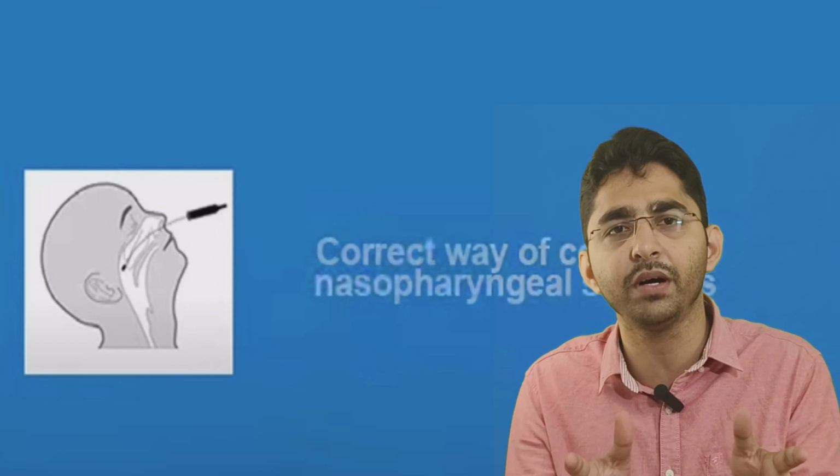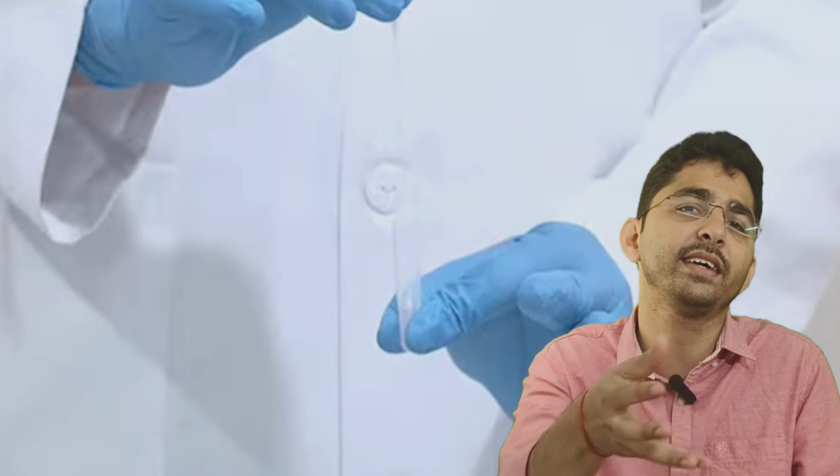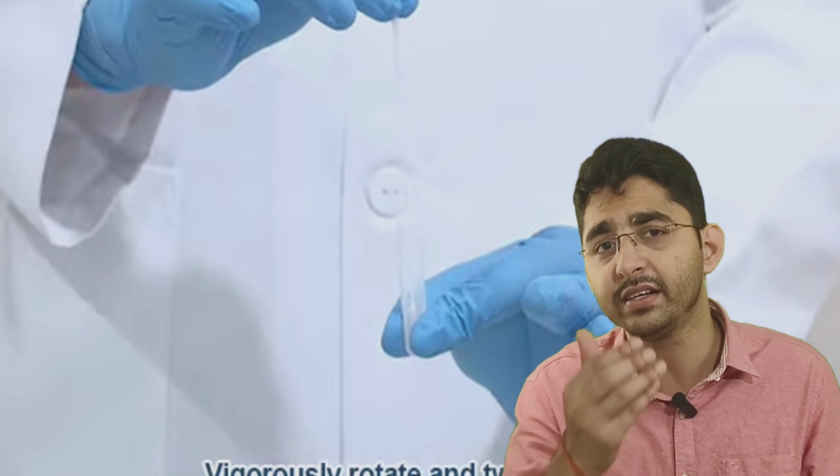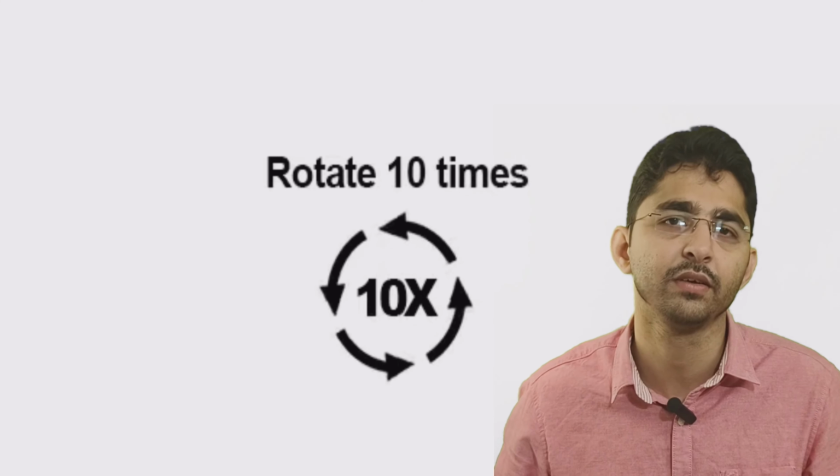So I am not going to talk about the IFU in detail, rather I am going to tell you what the WHO PQ team looks for inside the IFU. For example, what is the intended use, what is the specimen type, what are the sample volumes, what is the intended target population, and so many more things.